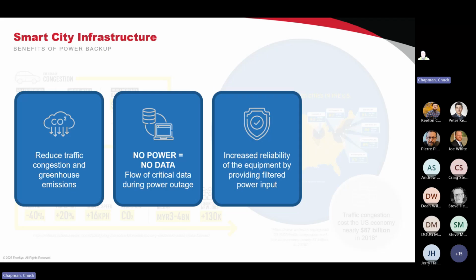There's increased reliability of the equipment, given by two factors: one, you are monitoring the equipment; two, you're monitoring the power that's powering the equipment. So when a condition happens, let's say an extended utility outage, you can jump in and dispatch a generator to that site before there's a long-term outage.